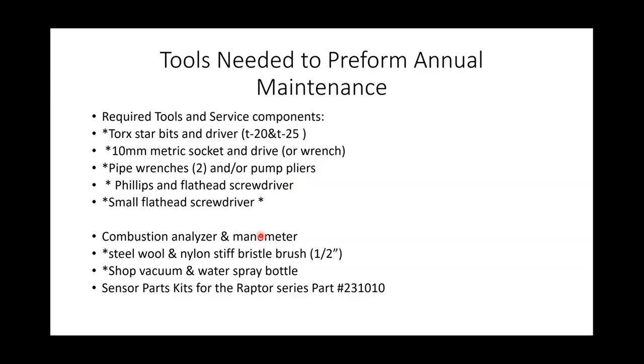So, first, in order to perform this annual maintenance, which is strongly suggested, we're going to need a few tools. We need some Torx bits, a T20 and a T25, a 10 millimeter socket or an open-ended wrench for 10 millimeter, 2 pipe wrenches, adjustable pump pliers, something to loosen the flexible connectors, a Phillips head and a flathead screwdriver, and a really small flathead screwdriver like a number 2 electrical screwdriver. A combustion analyzer and a manometer. We're going to want to take a combustion reading before and after the cleaning service to see where we're at. Steel wool, a stiff nylon bristle brush, a shop vac, a water spray bottle, a sensor parts kit, zip ties, and or some weed whacker string.